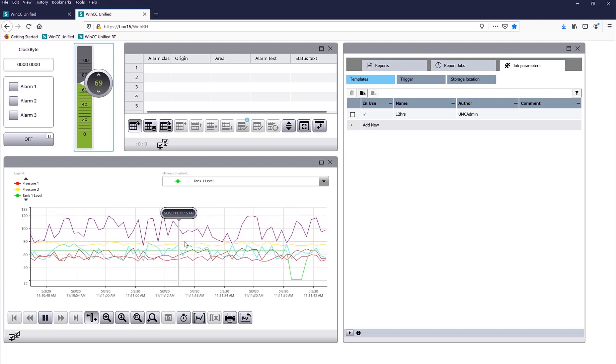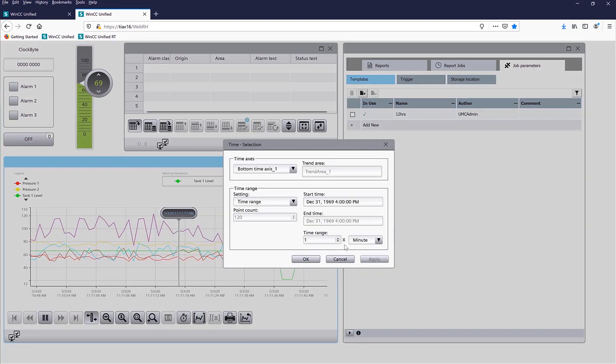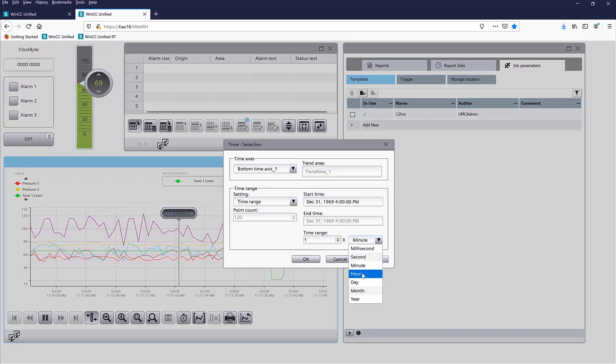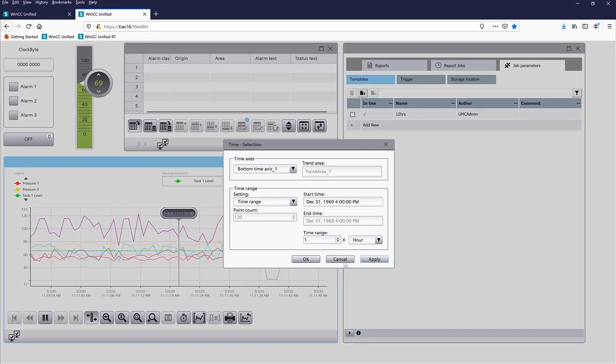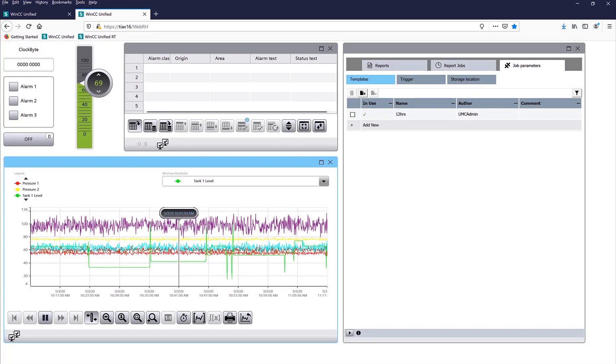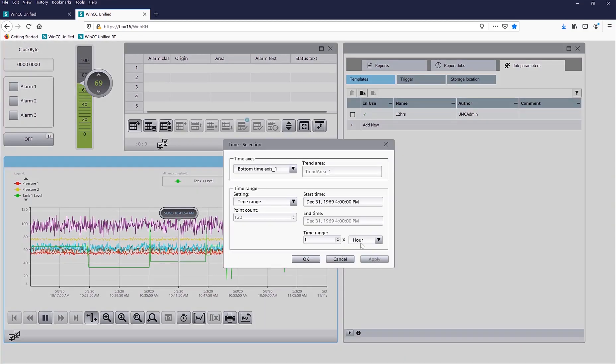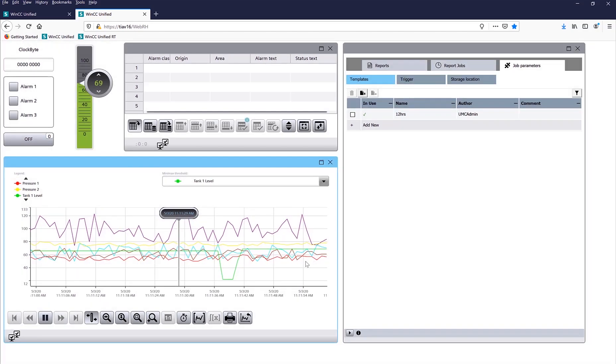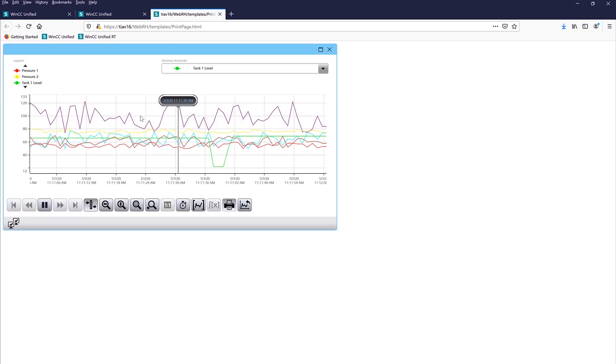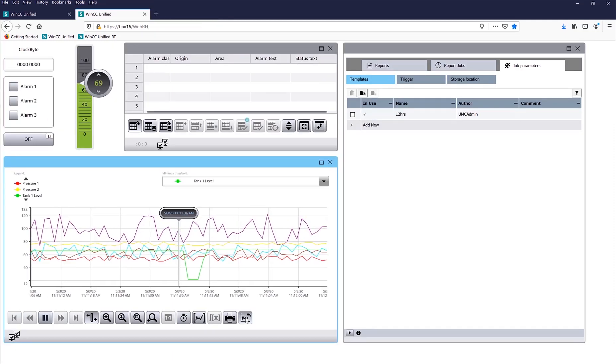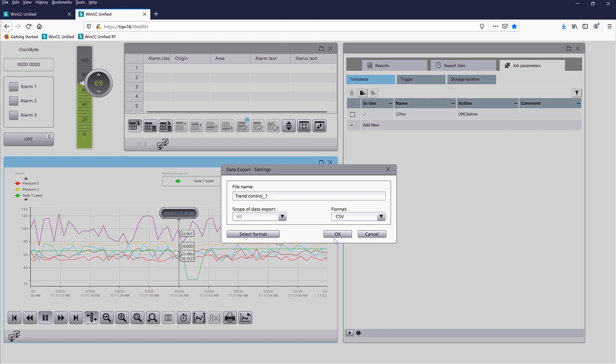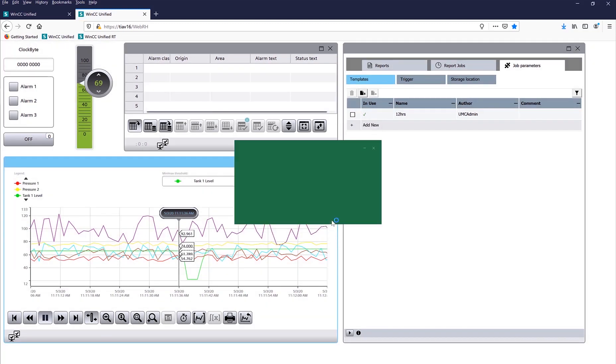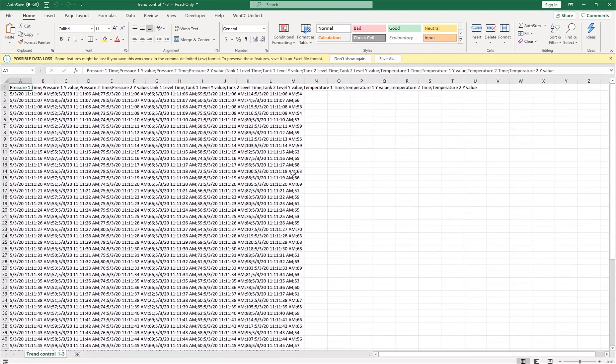What's nice about this Trend object is I can change the way it looks, so I can go ahead and simply say OK, show me by the hour, hit OK, so it's hourly, or I can go back to minutes. Or I can say print it, so now I can simply take a snapshot of whatever I was looking on the Trend screen, or I can export everything to a CSV file, and it's all done easily without any programming. It's all built in within the TrendControl object.